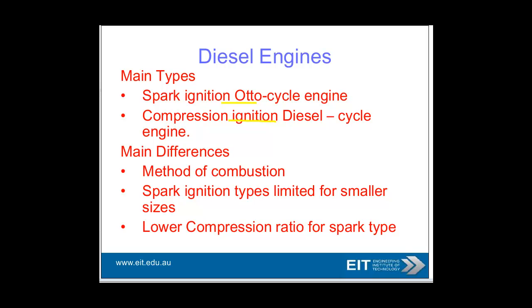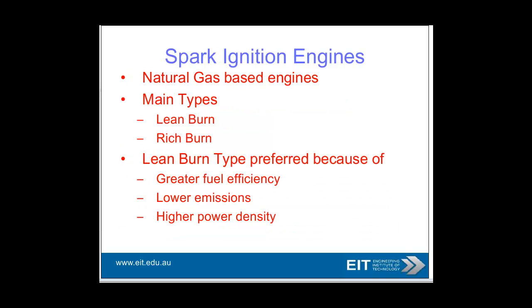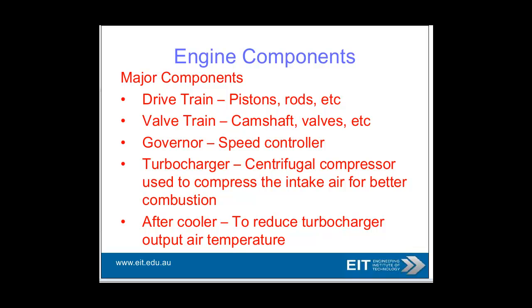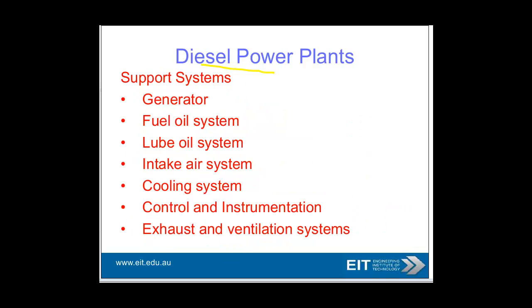Diesel engines: spark ignition and compression ignition. Spark ignition is natural gas-based, lean burn or rich burn, two types. Lean burn is preferred because of the greater fuel efficiency. Engine components typically are the drive train, which is your pistons and rods, the valve train, the good old camshaft and valves, and the governor. Speed control is very important, often connected to your PLC, programmable logic controller. There's a turbocharger to compress the intake air for better combustion, and the aftercooler to reduce the output air temperature. This can be one of the issues you have to watch out for. If you've got a very high temperature environment, you need to derate the engine. The diesel power plant also has support systems such as generator, fuel system, all the way through to control instrumentation and exhaust and ventilation systems.